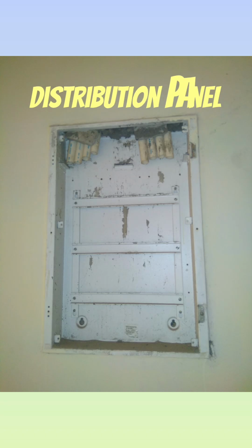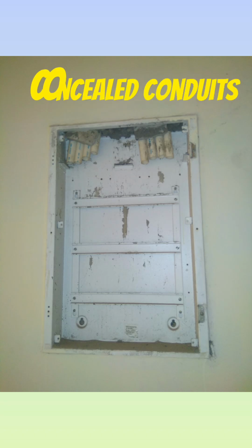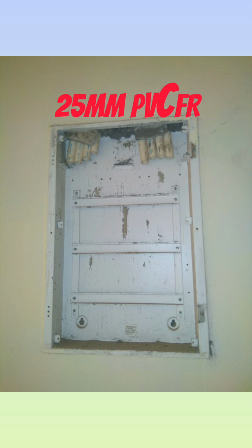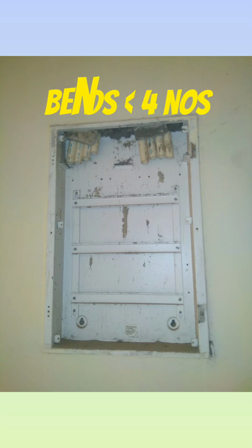For final distribution, conduits are embedded in the slab. This photograph shows a DB during the civil stage with conduits terminating from the top. As per IS 732, all conduit must be free of burrs and cleaned with a mandrel before wire pulling. Number of bends between draw boxes shall not exceed 4.